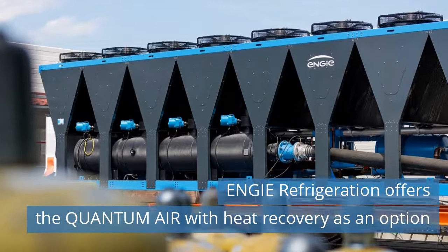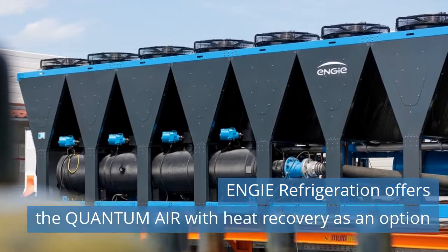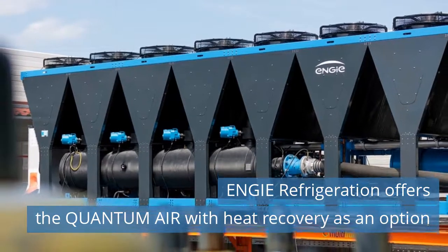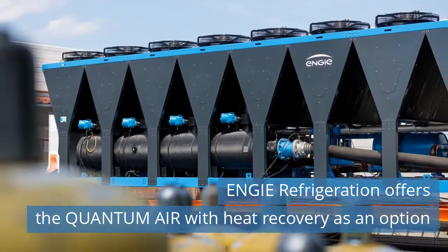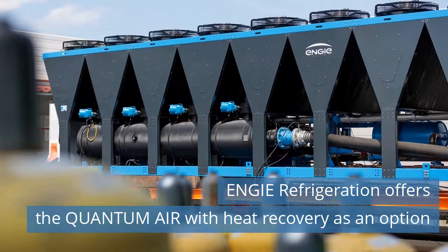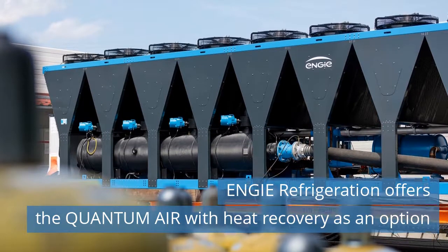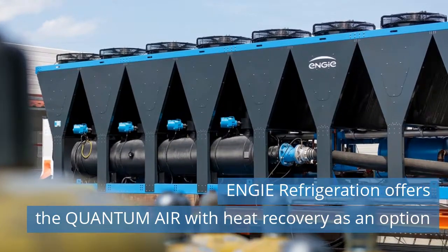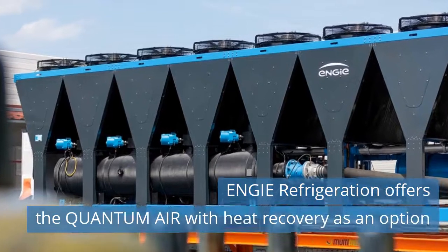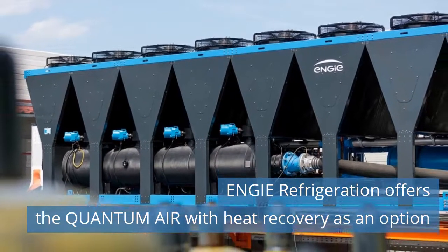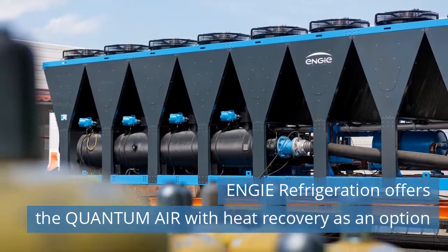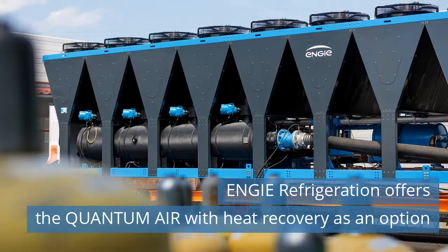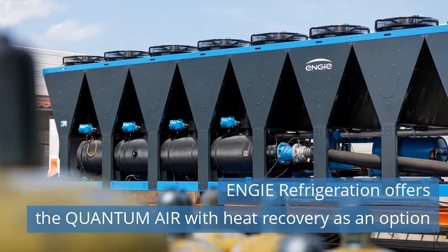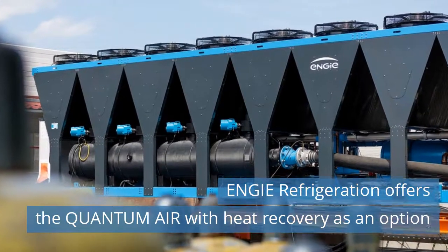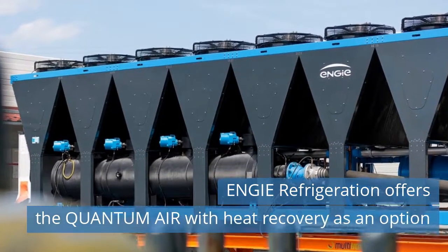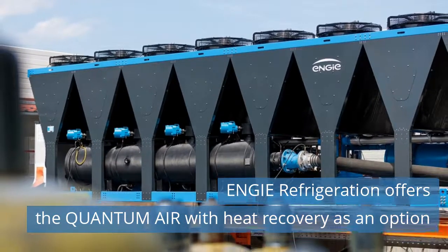The basis is an ingenious technical solution. The experts at ENGIE Refrigeration integrate an additional heat exchanger in the Quantum Air chiller. This exchanger makes it possible to conduct the heat generated during the cold generation process to a defined heat process, such as production hall heating or warm water supply in offices. Otherwise, this heat would be released into the environment unused via the air-cooled condensers. Users thus utilize free heat energy that they would otherwise have to obtain from an additional heat generator. This heat energy can be used either completely or partially in what is referred to as combined operation. To this end, the waste heat is transferred to a heat circuit via a parallel flooded shell and tube condenser. The chiller fans now run at partial load or not at all.